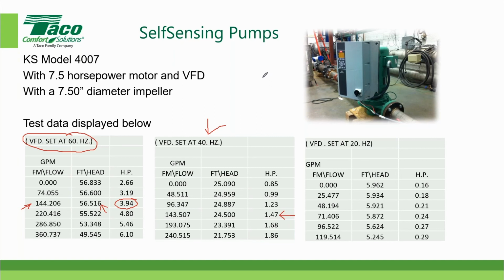Here's a question that did pop up. Is every individual pump tested? No, only a family of pumps are tested. So in this case, it's a KS model 4007 with a 7.5 horsepower motor and a 7.5 inch diameter impeller. Once we test it for that pump and create the accurate data, then all the other models that are identical, with the same impeller diameter and same horsepower motor, have the same characteristics. Now the characteristics can vary as much as 2 to 3%. But in terms of the overall operating characteristics of the pump, motor, and drive, it's insignificant.